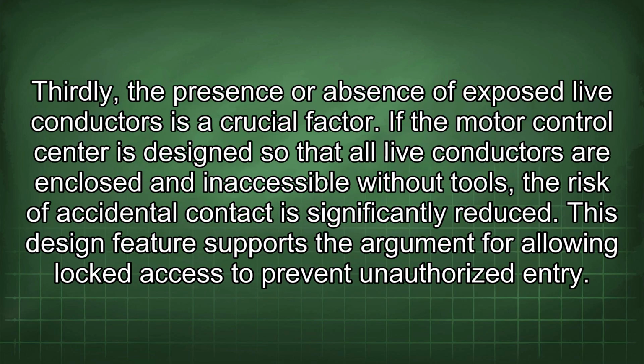Thirdly, the presence or absence of exposed live conductors is a crucial factor. If the motor control center is designed so that all live conductors are enclosed and inaccessible without tools, the risk of accidental contact is significantly reduced. This design feature supports the argument for allowing locked access to prevent unauthorized entry.